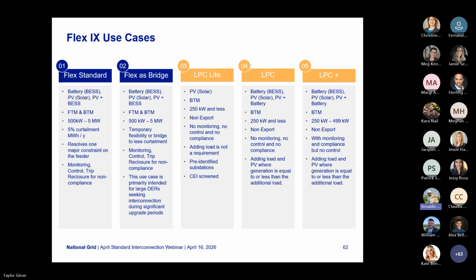For the example I mentioned, we will provide you in your flexible interconnection contract a 5% curtailment megawatt-hour figure, meaning throughout the year 5% of megawatt-hours will be curtailed, and ideally you will do the modeling to make sure that works for you. This resolves that one major constraint, the feeder, but it's not solving for others, so you'll still be studied for other potential issues. We'll also be adding monitoring, control, and trip recloser for non-compliance, as mentioned.